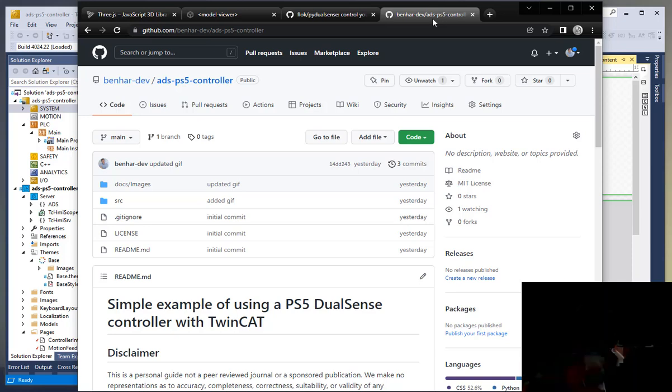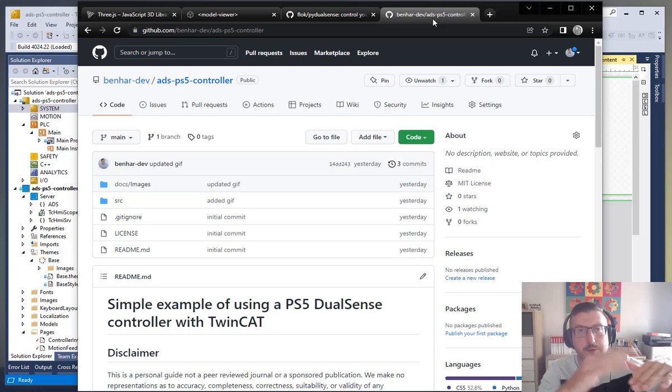But like I say, we've got the Python side that speaks to the controller. The controller speaks to TwinCAT via ADS, this ADS library that's available, and then the TwinCAT side all it does is hold a GVL, which holds all the symbols. Those symbols themselves, we move a few things around into a structure, just to make some of the graphs slightly easier to show. But otherwise, we then push it up into TwinCAT HMI. We'll see that in TwinCAT HMI, we've used the project generator, so the layout was all automatic.